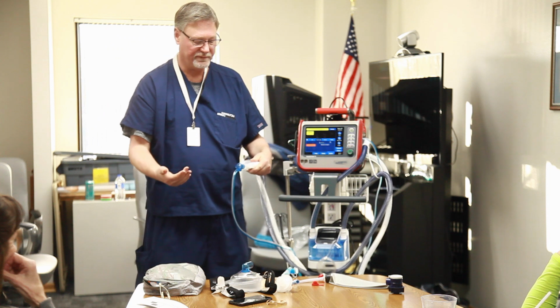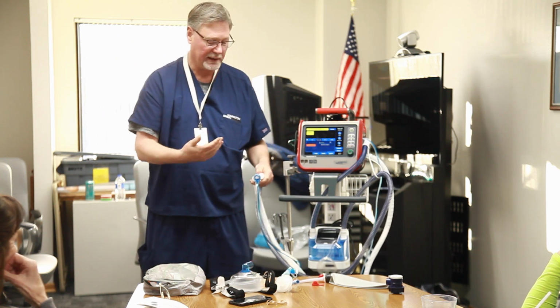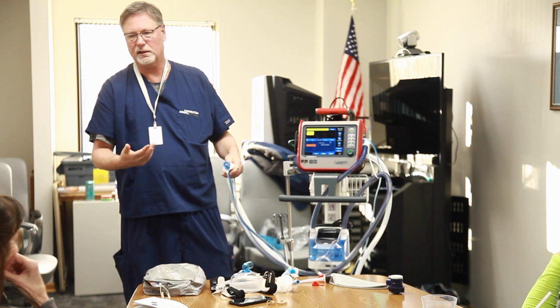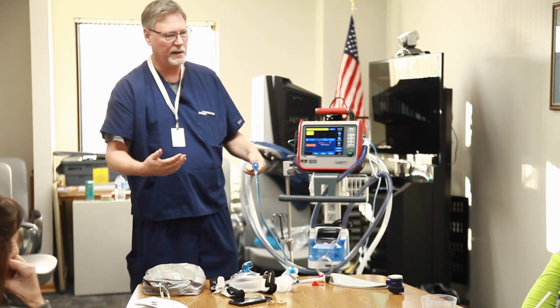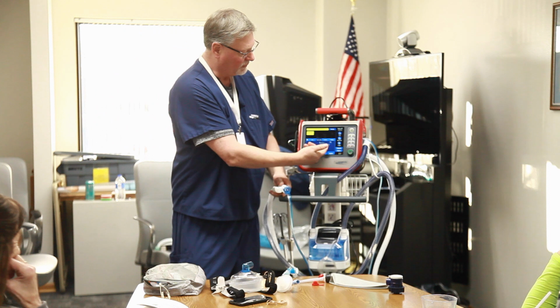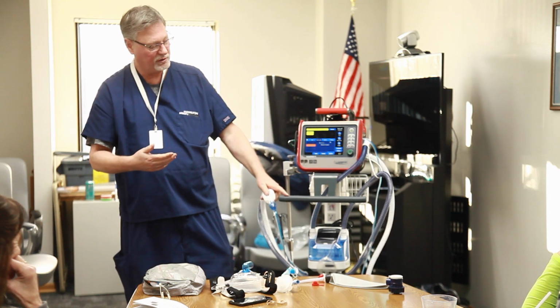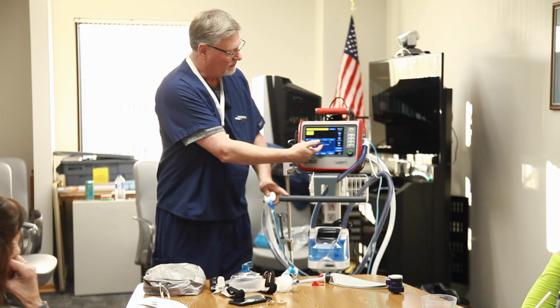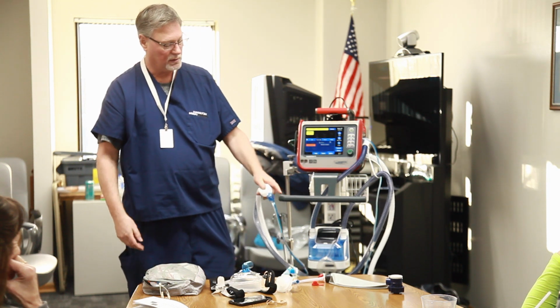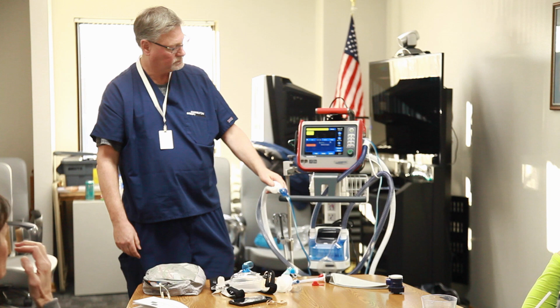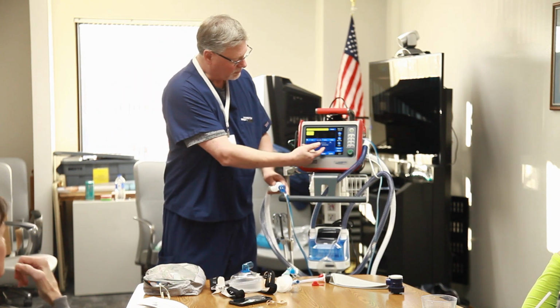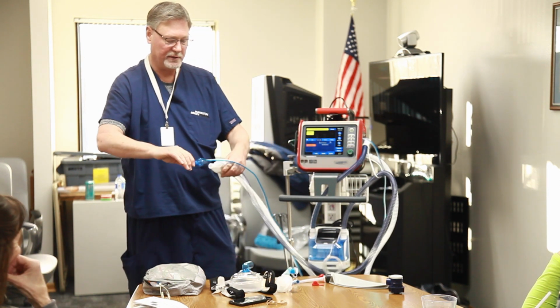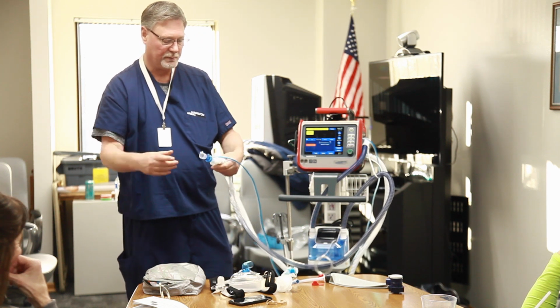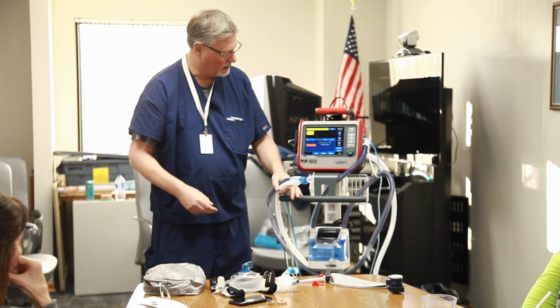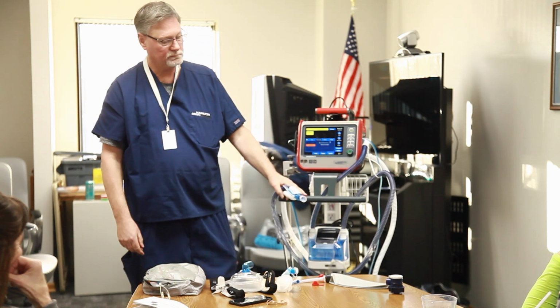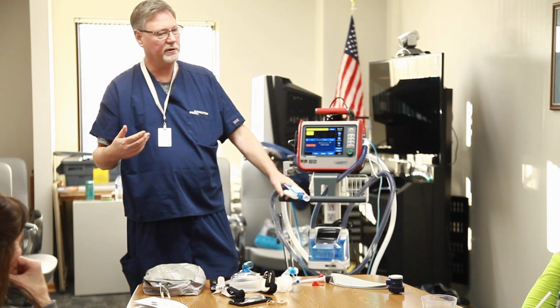Now this is a bidirectional flow sensor. It's sending information back, I can't quite fathom this, like 200 times a second. Flows, volumes, pressures, all that kind of stuff. So maneuver is in progress. You're going to get a few whooshes here in just a few seconds. Then it's going to tell me to turn the flow sensor again. Turn the flow sensor, everything, the adapter and everything. Turn it back over. Hopefully I didn't take too long. Maneuver in progress yet. And if everything is calibrated, you're going to get a green check mark.